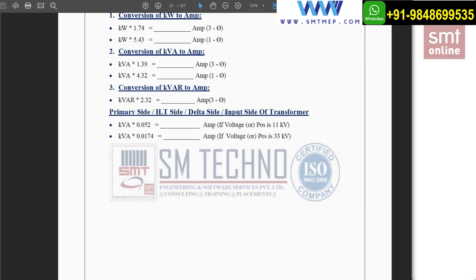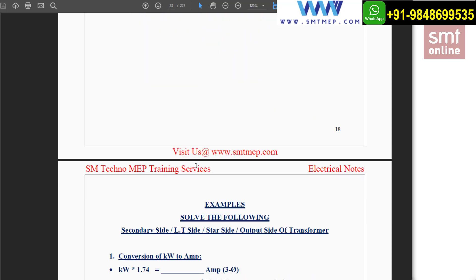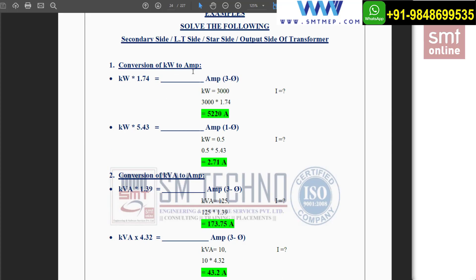For the input side of the transformer — also called the delta side, high tension side, or primary side — the method is as follows. For example, if your transformer is 500 KVA and the point of supply is 11 KV, that means you are giving that voltage on the input side. Multiply the transformer size with 0.052 to get the current value. When the input side voltage is 33 KV, multiply the transformer size with 0.0174 to get the current value.